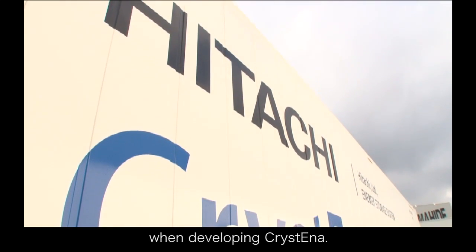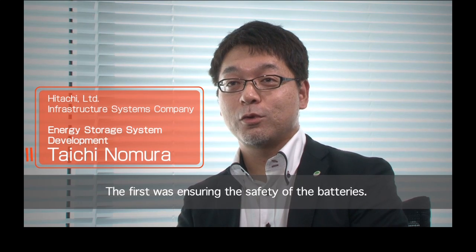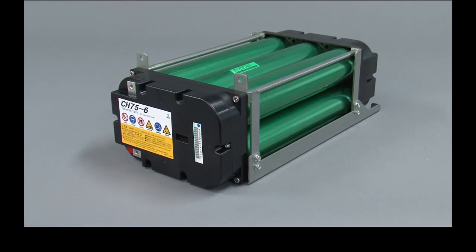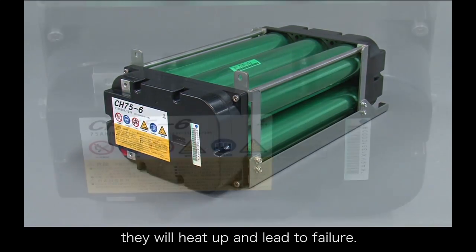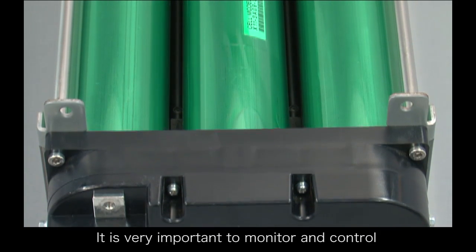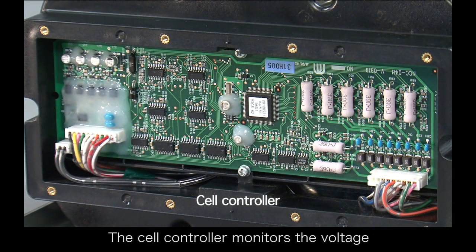There were two big technical challenges when developing CrystEna. The first is how do we protect the electricity system? The second is how do we predict the capacity and control the battery? Lithium-ion batteries are high performance, but if the batteries are handled improperly, they will heat up and lead to failure. It is very important to monitor and control the operating conditions constantly. This role is taken on by the cell controller, which monitors the voltage and temperature conditions of each battery. Voltage and temperature information is acquired by the battery management unit mounted on the top of each battery panel, enabling constant monitoring of operation.